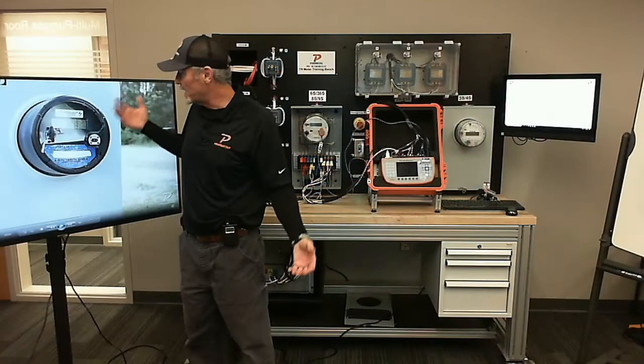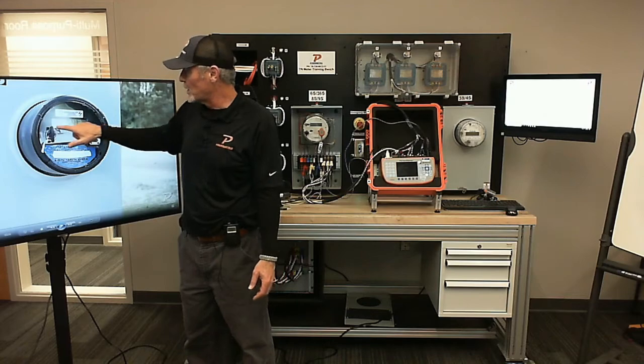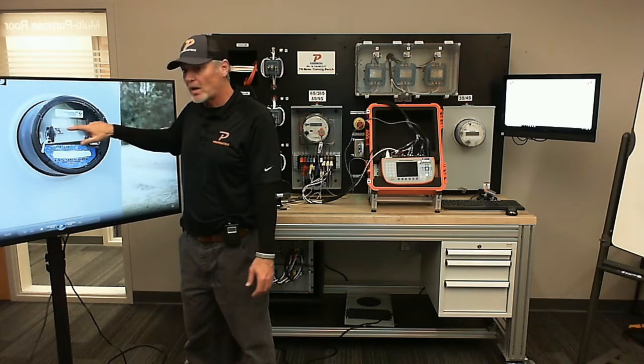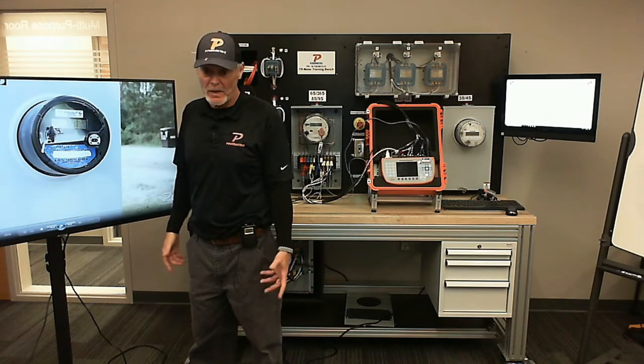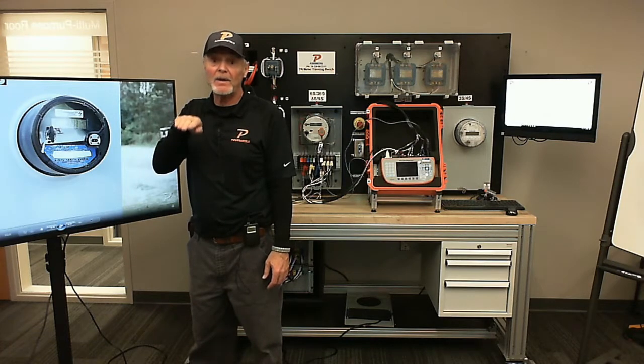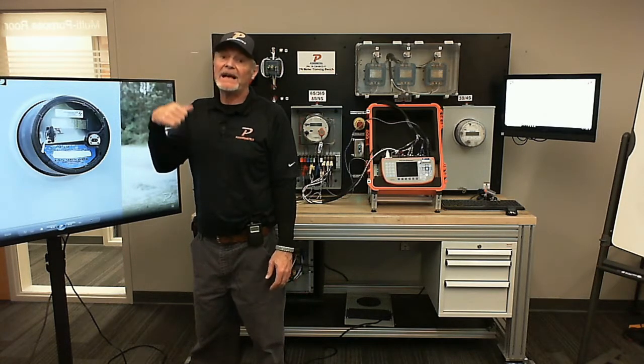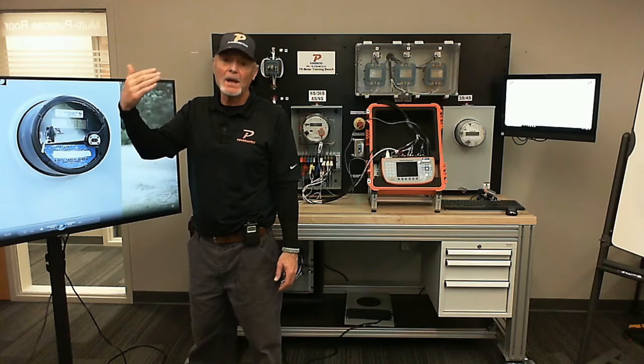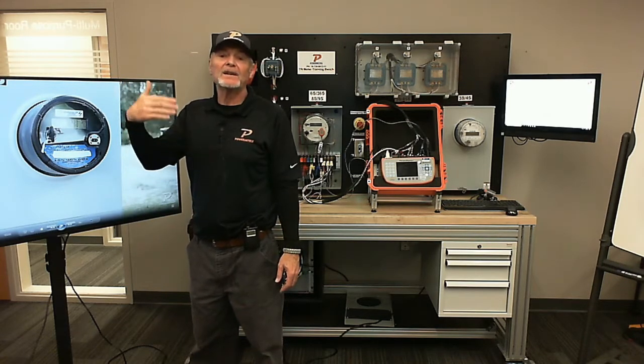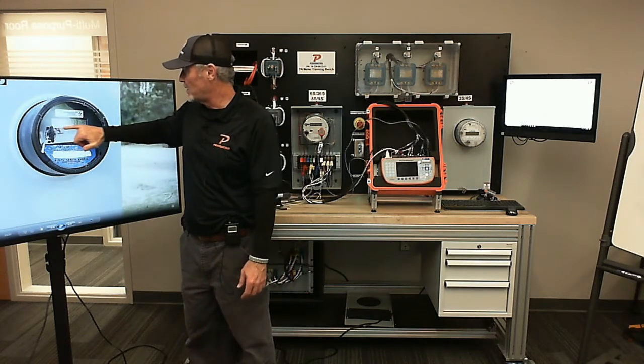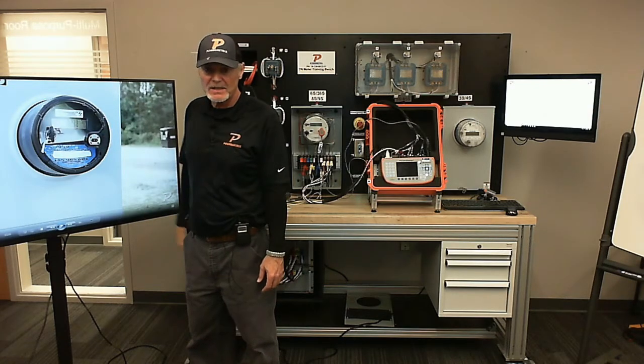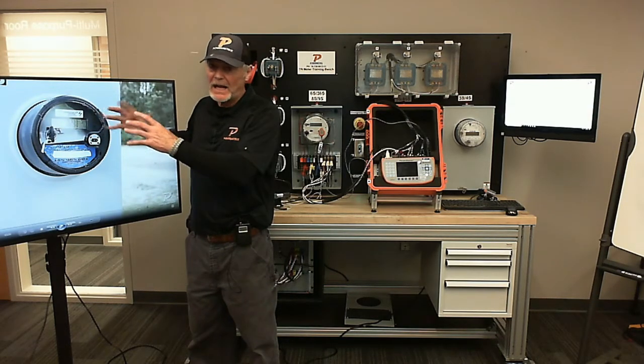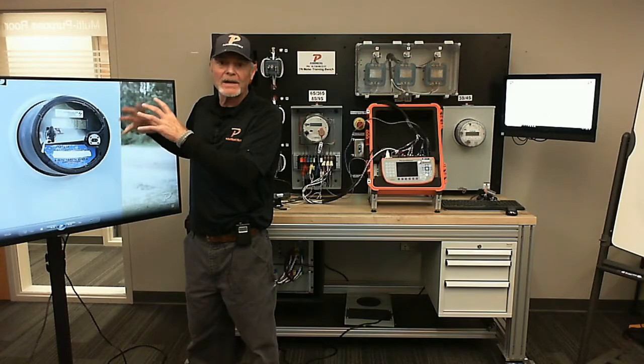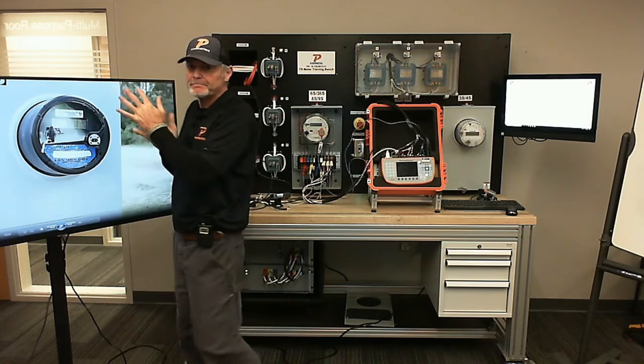Another thing you can look for, I can look for my bar going across there to see if I've got much load on there as well. If it's not moving and I don't have any load there, then I know that I'm probably going to have to perform a phantom load test, right? And I can't do a customer load test because I don't have any movement across there. Okay, so all of that stuff, I haven't even cracked anything open yet, and already I know all that information. Okay? Thanks, bud.